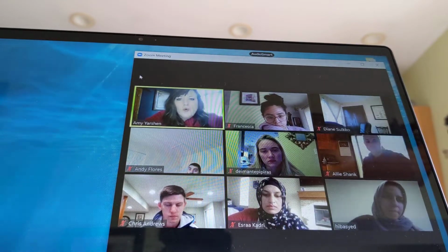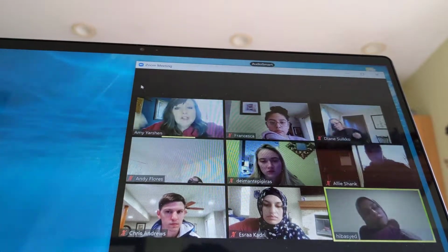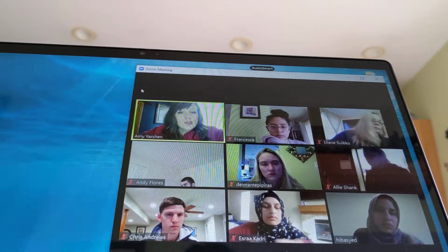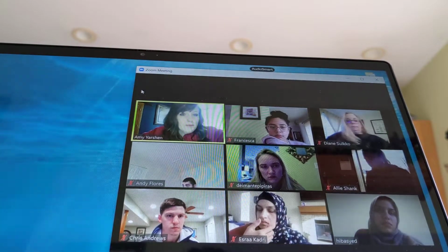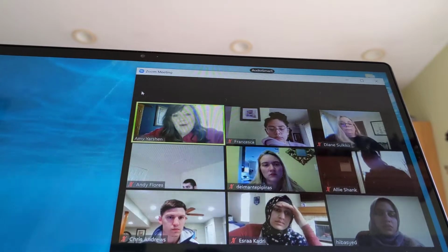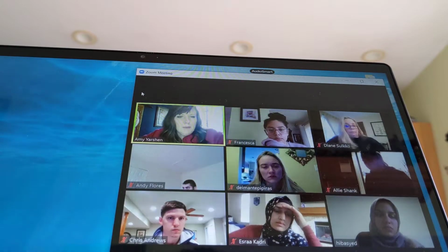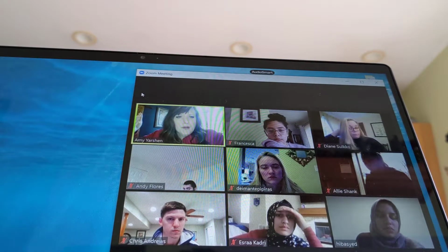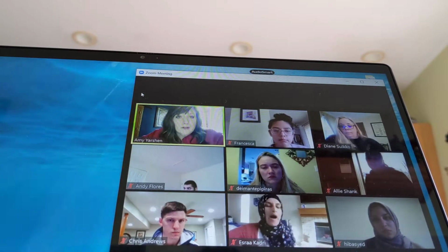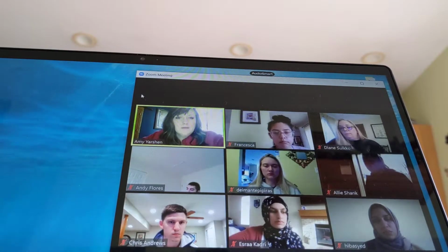More general. So you do a daily uniformity flood, and then you might do a high count flood, but not as often. The daily one is usually less counts, right? Most of you did like a 2 million flood daily. Whereas if you did a high count flood, someone did the minimum number. I forget who it was. 30 million is usually the minimum for a high count. Some of you do a 200 million. But the minimum for systems is usually at least 30 million for a high count flood.